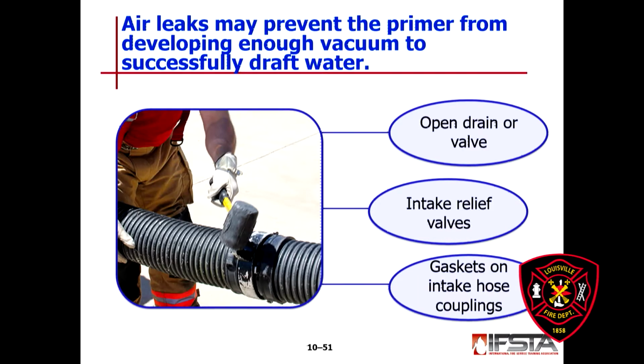If you're working 10 to 20 feet of lift, then it may take a little bit longer. But if you haven't gotten a prime within 30 to 45 seconds, then you need to stop and trace the problem. The most common problem, as I said earlier, for a pump having issues with drafting is air leaks. You can have air leaks from an open drain or an open discharge. If the valves on your discharges or other intakes have corroded a little bit, you have air leaking around them. Your intake relief valve or the gaskets on the intake hose couplings themselves can all be sources of leaks, allowing air to get in and not allowing you to get a good draft.